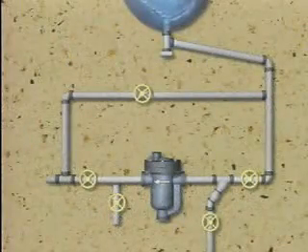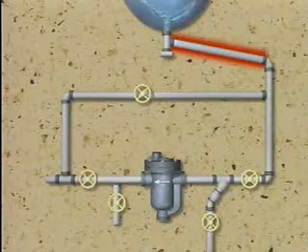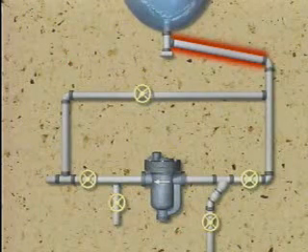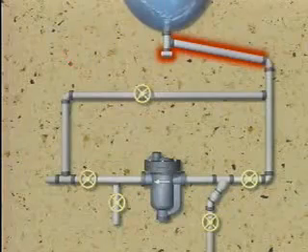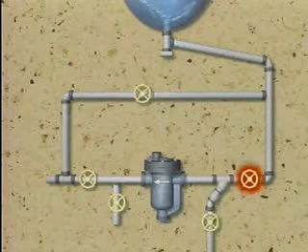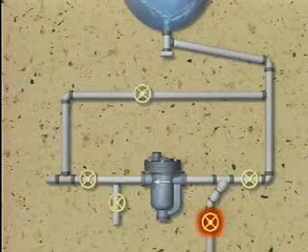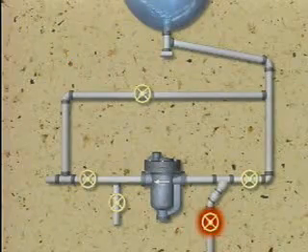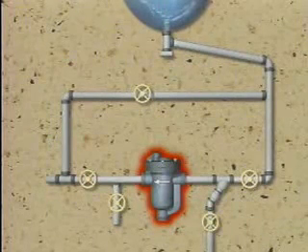A drip line connects to the lowest point of the steam line or process equipment through which live steam moves. Condensate collects in the drip line. A typical drip line also includes a dirt pocket to trap some of the larger particles of dirt or scale that may be dislodged in the steam lines or the drip line. An inlet valve isolates the steam trap inlet from the steam line. A strainer near the inlet valve prevents dirt and scale from entering the steam trap. The next component is the steam trap itself.